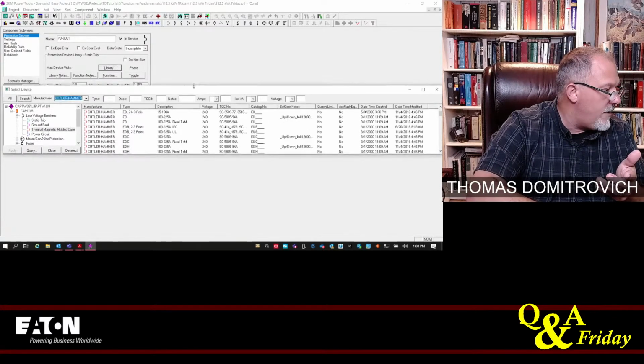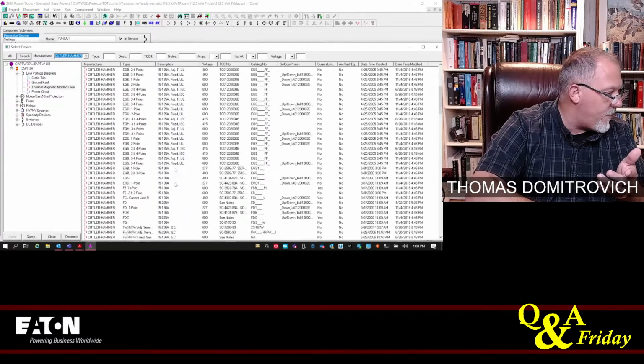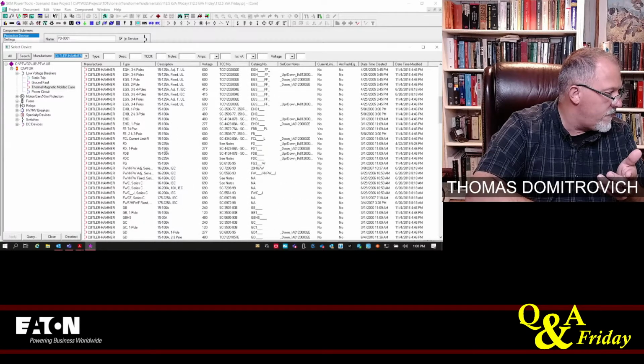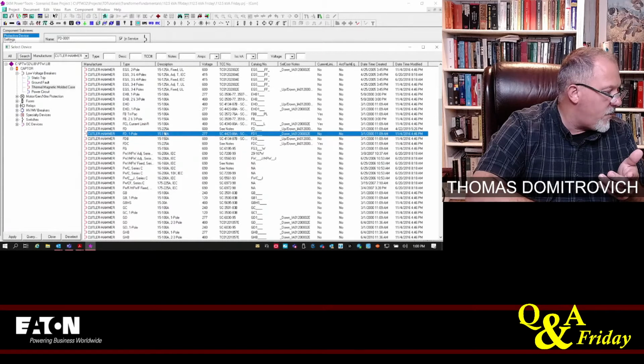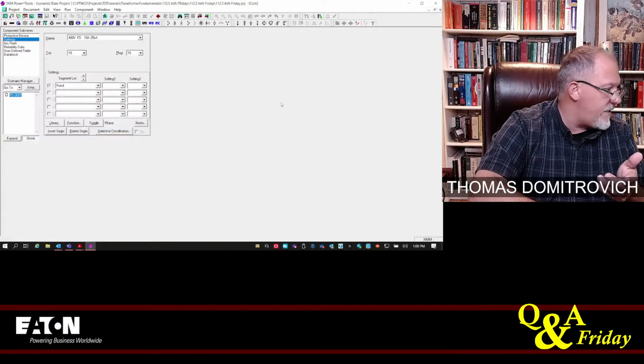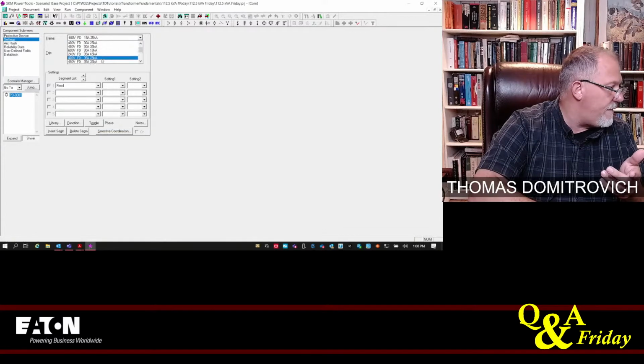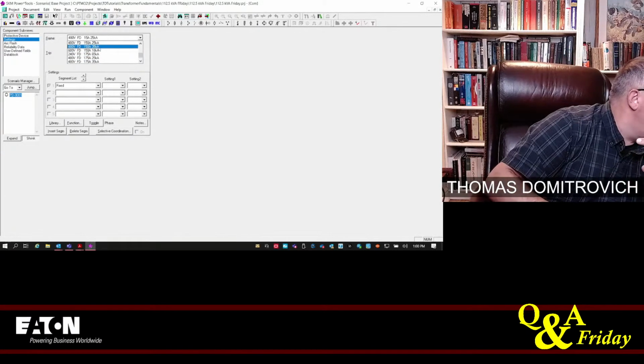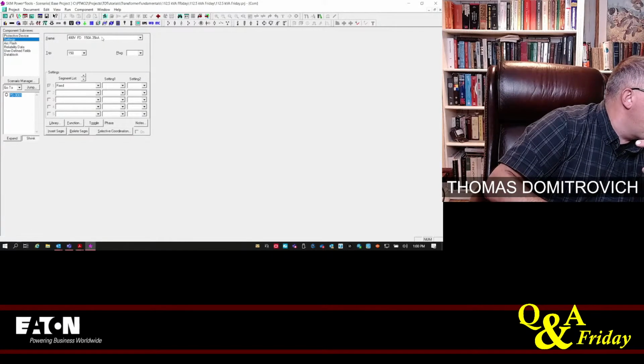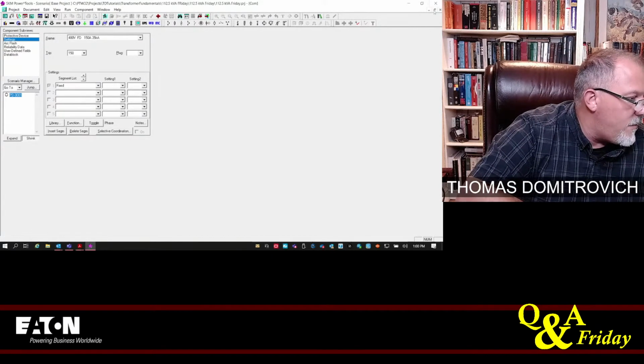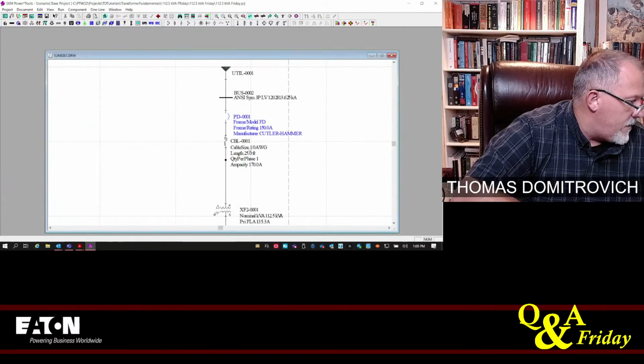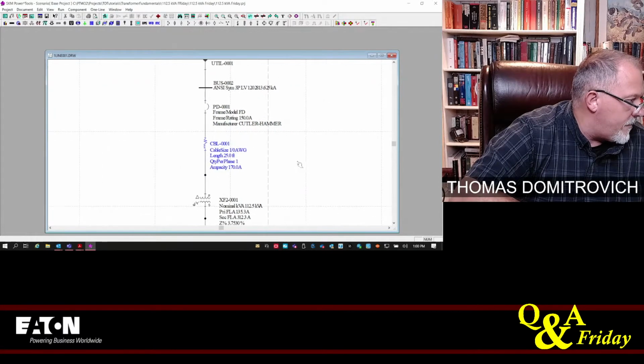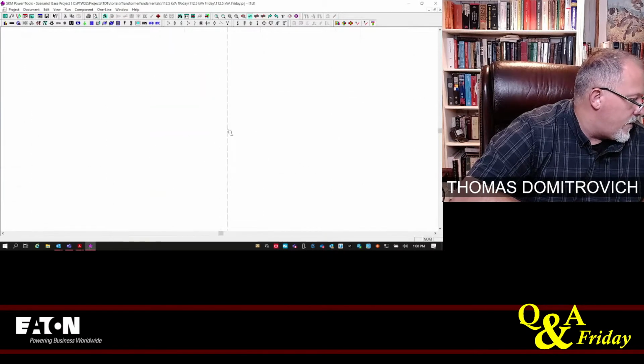So what I'm looking for is a 150 amp breaker. I can get that's an FD single pole, an FD breaker. Let's do an FD breaker. FD 150. So I'm going to pick up an FD 150. All right, so I got an FD 150. Down a little. So that is an FD 150.